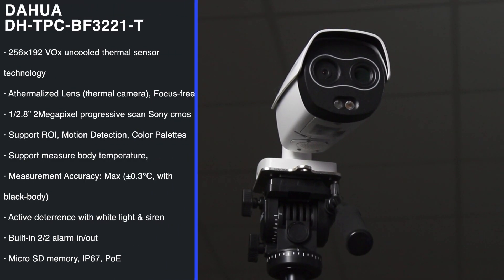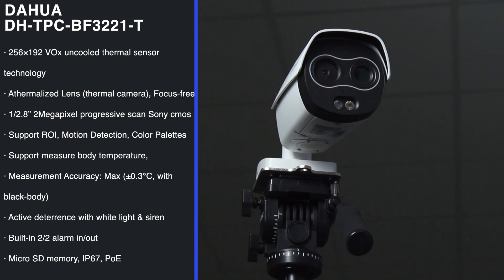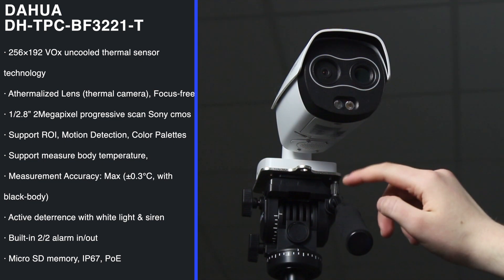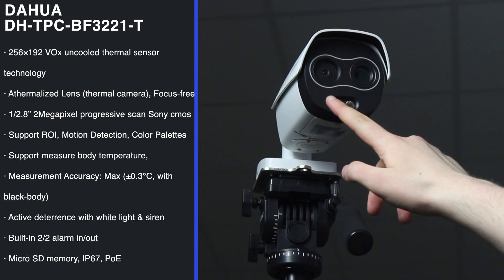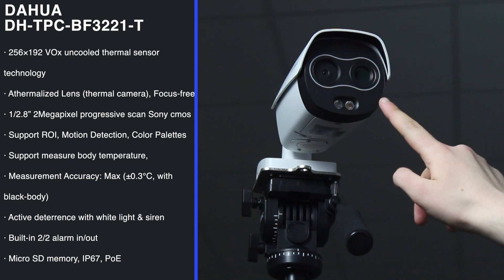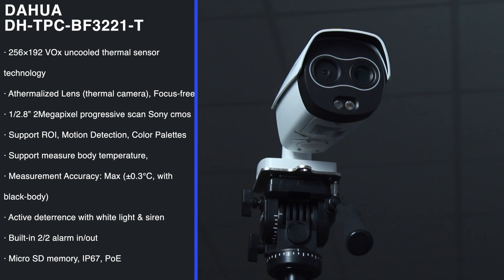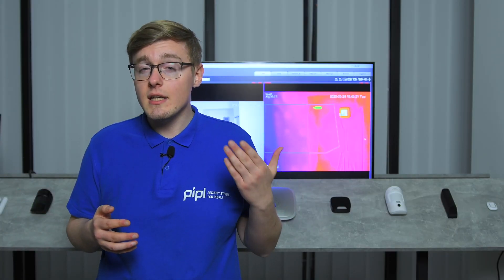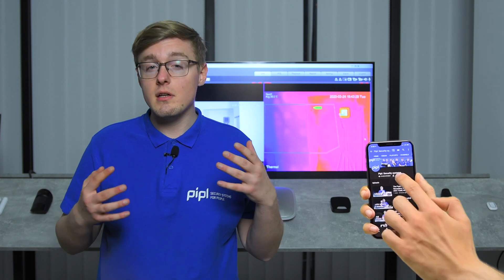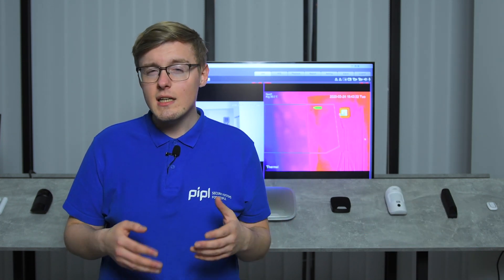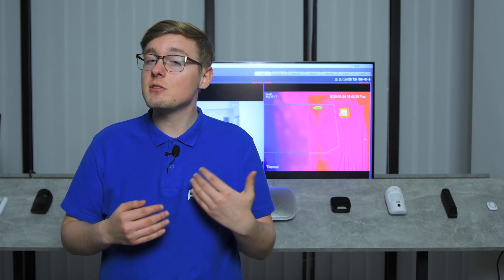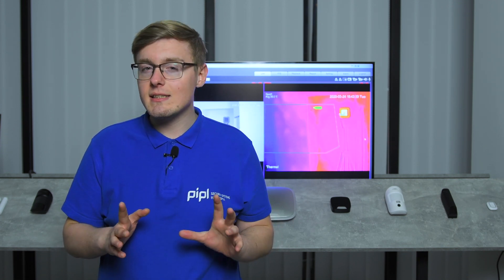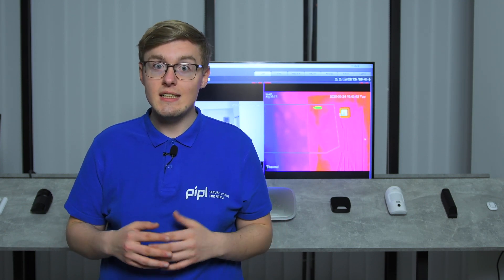The camera we have is Dahua TPC-BF3221-T thermal hybrid network camera that is able to measure human body temperature due to its dual camera setup, consisting of a normal camera module with an infrared LED and a thermal camera module all together in one body. The peculiarity is that the camera ignores that people may wear masks or helmets, it just doesn't affect the measuring accuracy. It also does not measure temperature of hot liquid like tea or coffee that a person could carry. The measuring ability applies to people only with 30 maximum people number in camera's sight. And of course, there is a certain imprecision probability, but with a blackbody device it would not exceed more than plus or minus 0.2 or 0.3 Celsius.